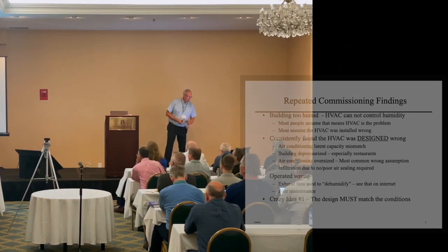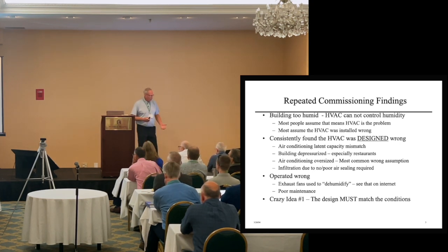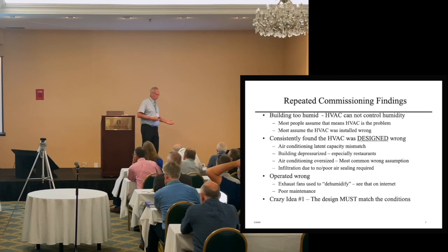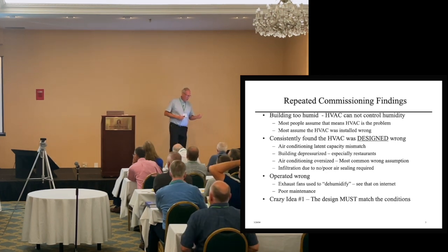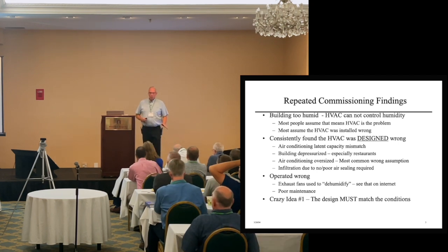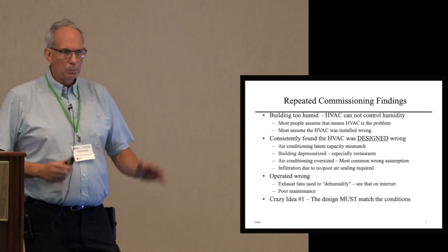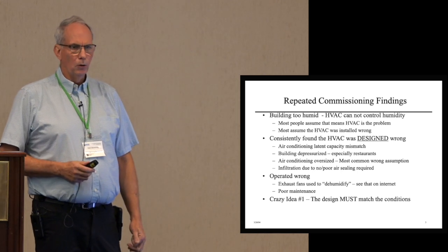Okay. I'm just trying to transition from commissioning to expert witness work. So we had repeated commissioning findings. Starting off, we had buildings that were too humid. We still do. And this is uncomfortably humid. The first library I worked on hadn't even opened yet, and they were putting books on the shelves and we were throwing them away because of all the mold they were growing.